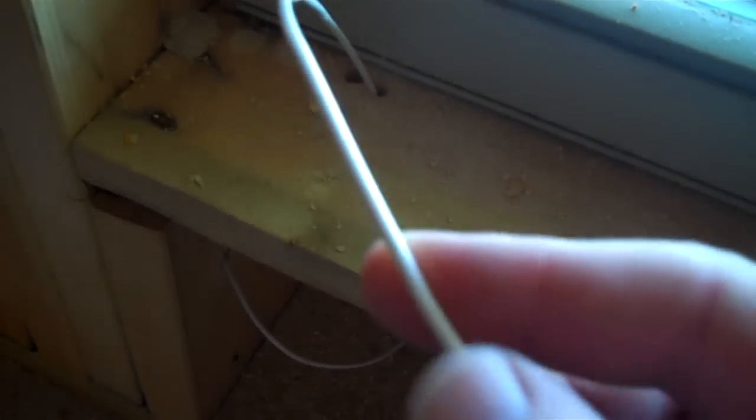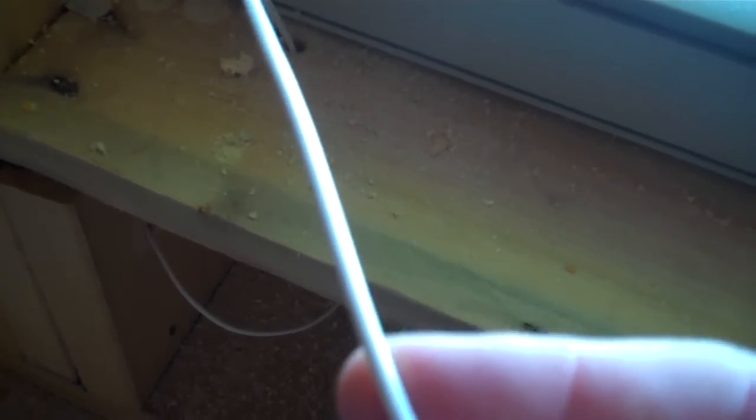Now, the wire that we're using here is a 22-gauge four-conductor wire, so there are four teeny wires in there. The contact itself only requires two wires, but we always got into the habit of using a four-conductor because other devices on the alarm system require four conductors, and it's nice to have a backup pair for whatever reason.